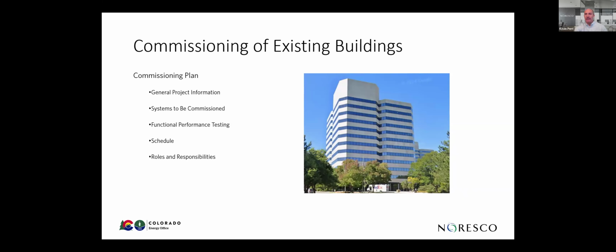General project information, what systems need to be commissioned. So again, that's going back to the beginning of the presentation when we said, we're going to follow this standard. We're going to commission these systems, mechanical, electrical, plumbing, and it's going to be domestic water heating, air handling units, rooftop units, you name it. That's all that info should be in there. The functional performance tests. So how you're going to test them. So your sequences of operation, the schedule on when you're going to test. You're allowed to do deferred testing if the weather doesn't cooperate for one season or the other. And then the roles and responsibilities of the team.